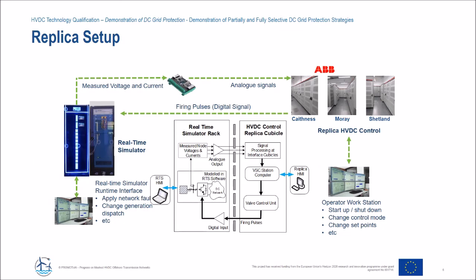So in parallel to using the generic converter models, what we have here at the HVDC Centre is the replica control and protection cubicles for that Caithness Moray Shetland scheme that I mentioned earlier. What this means is the full single line is still modelled in the real-time simulator, but the controls of the converters are now actually replicas of the real system. So it's a similar setup to the IEDs where you feed out the system voltages and currents, but in this instance we're getting the firing pulses for the valves back in, and that's how that's in the loop for this real-time testing.